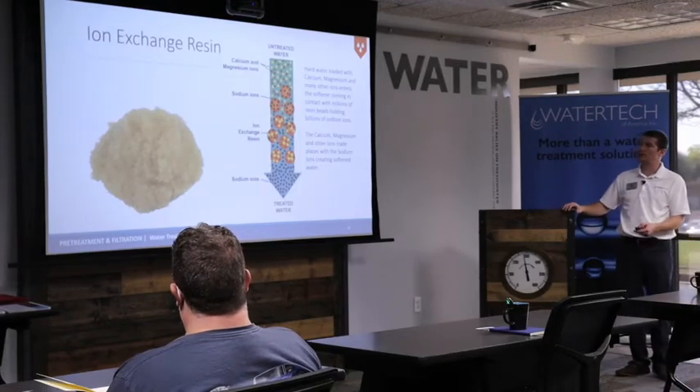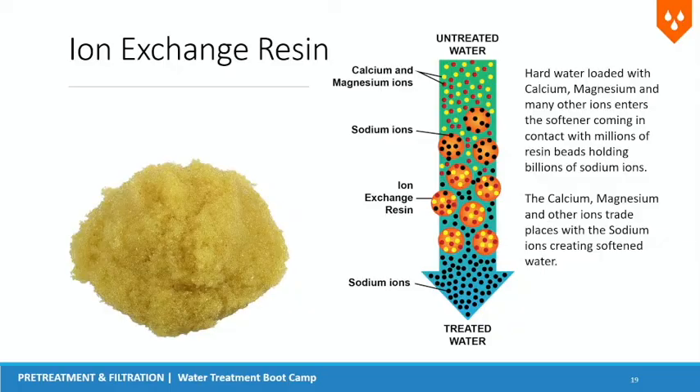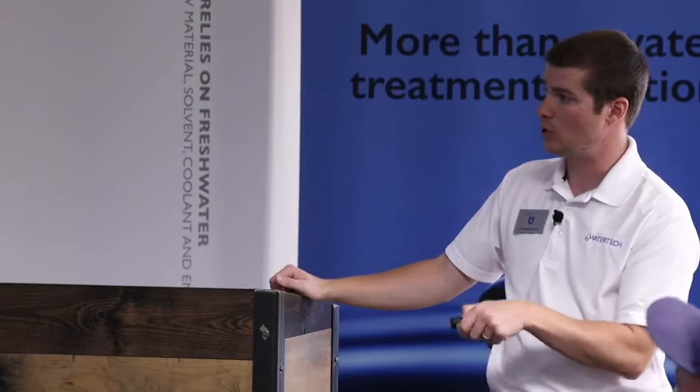How do we soften water? Inside those softeners is a cation exchange resin — a negatively charged resin. Calcium, magnesium, and iron are positively charged, so they're naturally attracted to it. The resin is loaded with sodium ions, which have a plus-one charge. Calcium, magnesium, and iron may have a plus-two or plus-three charge, so they're stronger — they kick the sodium ions off the resin and bond to it. That's how we pull those minerals out — we put sodium into the water in exchange for removing calcium, magnesium, and iron.